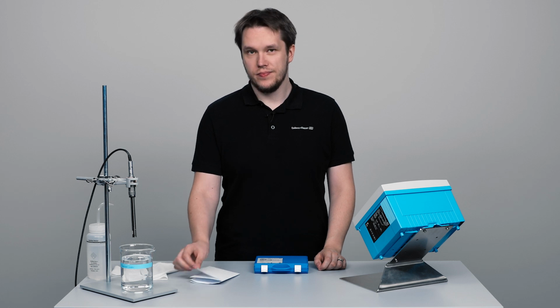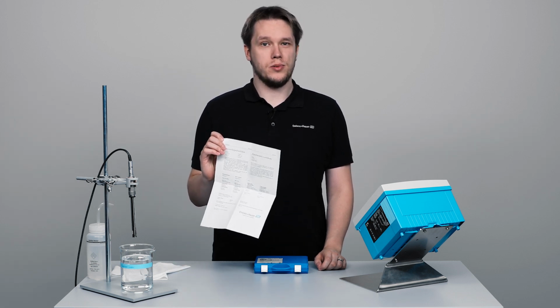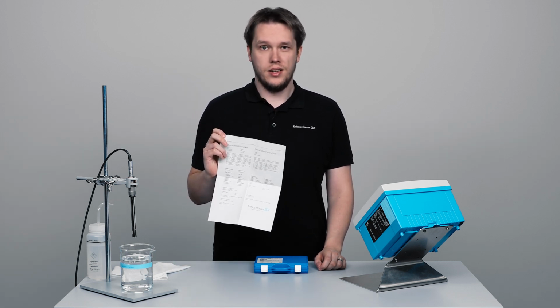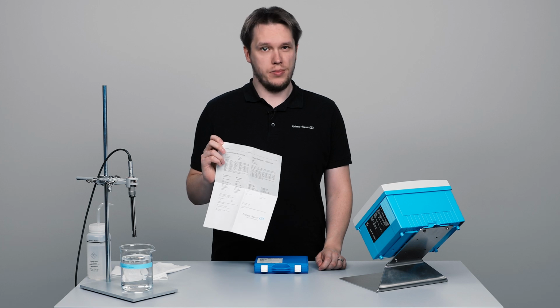The sensor must be clean and free of coatings, and the system must be powered for at least 15 minutes to ensure the sensor is ready to go. First, enter the absorption values from the certificate into the sensor input menu in the calibration settings. Enable the filter option by selecting yes and enter the filter values.